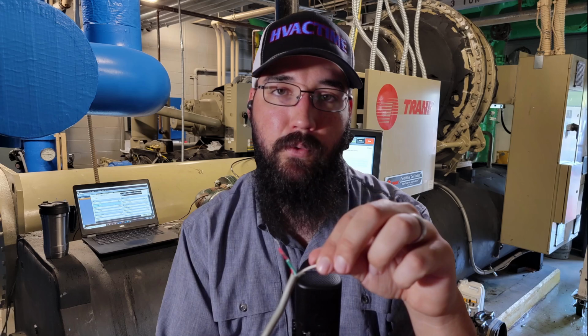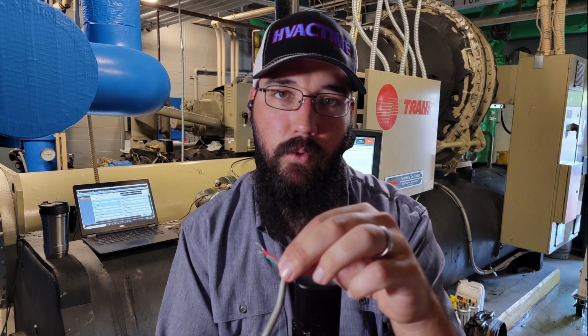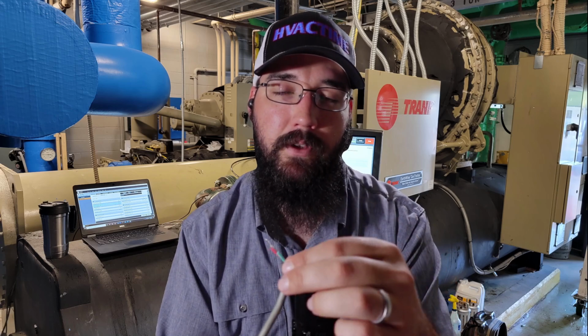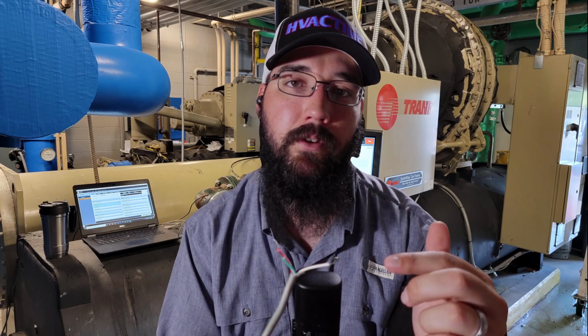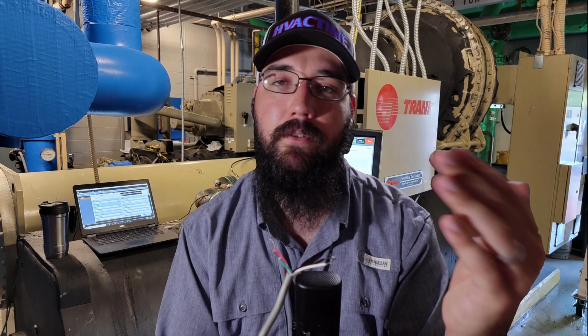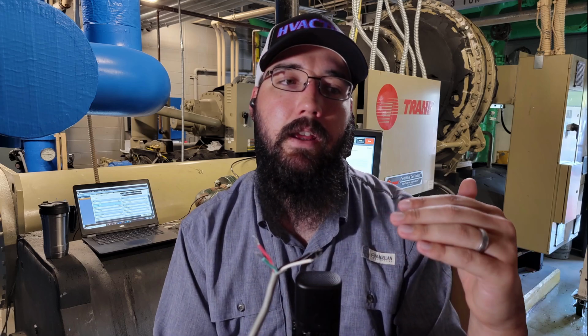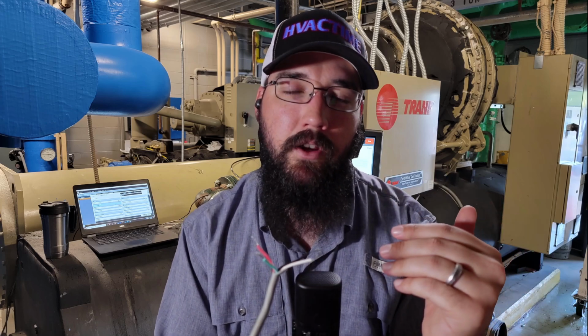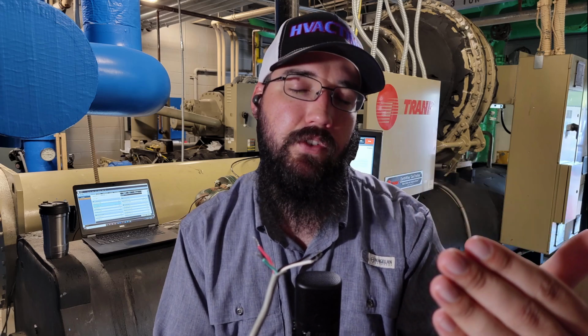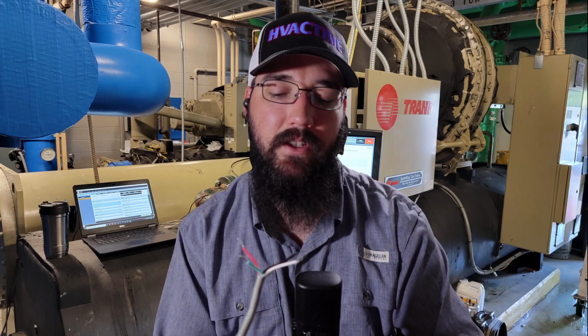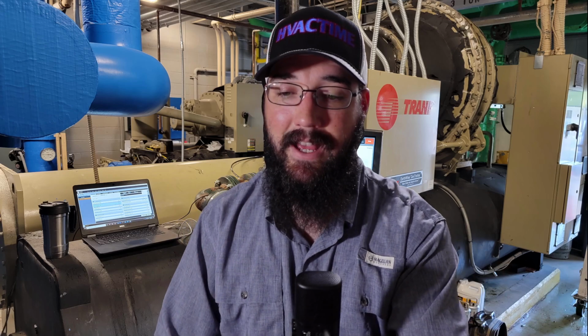And even between this 4 wire, the two stator coils will have the same ohm value. These would have 50 ohms across both of them, if this one was good. In the same way on the 5 wire, each of those are going to have the same ohm value. So if it was 20 ohms between each coil, then you want to see that. And if you have one that doesn't have that, that would be an indicator of a failure.